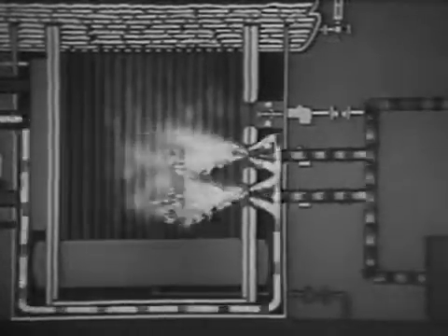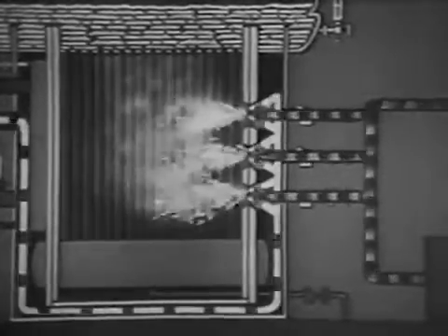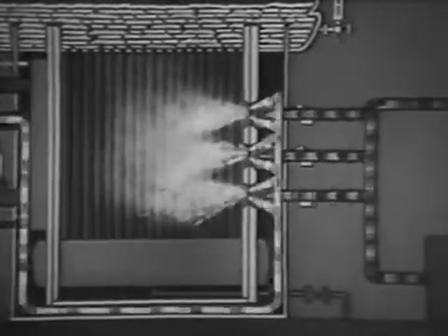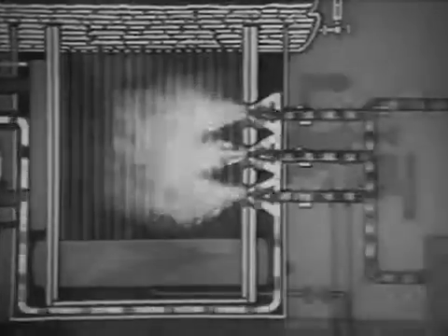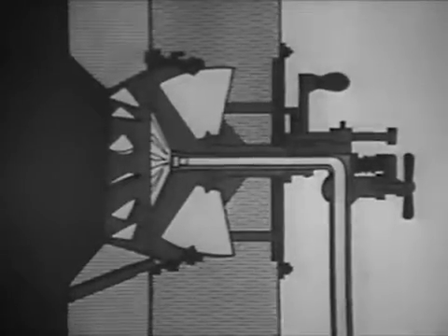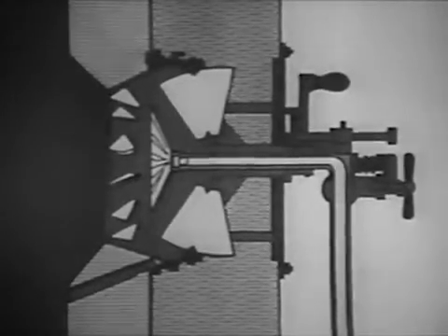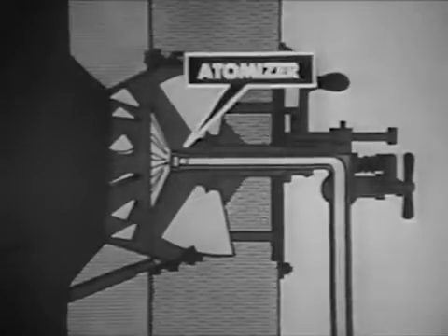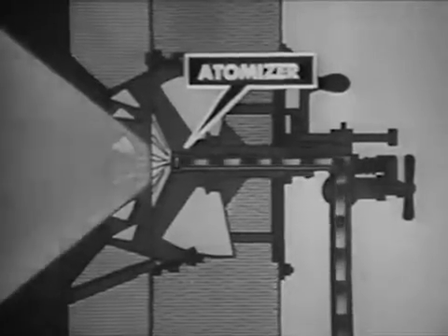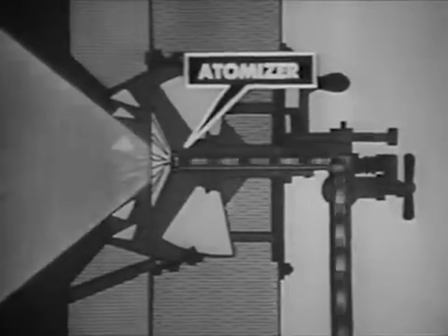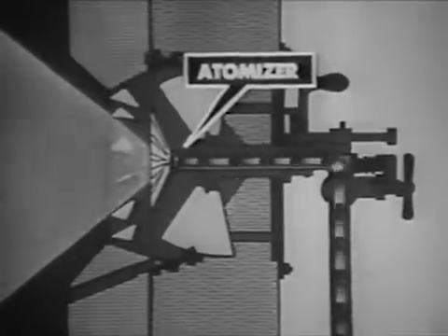As seen, the burners in a boiler provide the combustible mixture of air and fuel oil that is burned in the boiler furnace. As seen in this view of a typical burner mounted in a furnace wall, the burner's atomizer reduces the fuel oil to finely divided mist-like particles. That is, atomizes the fuel oil.